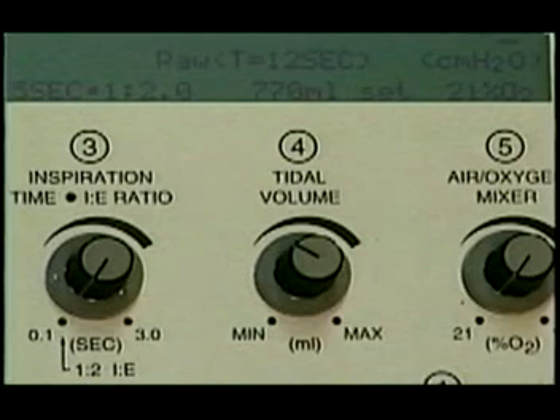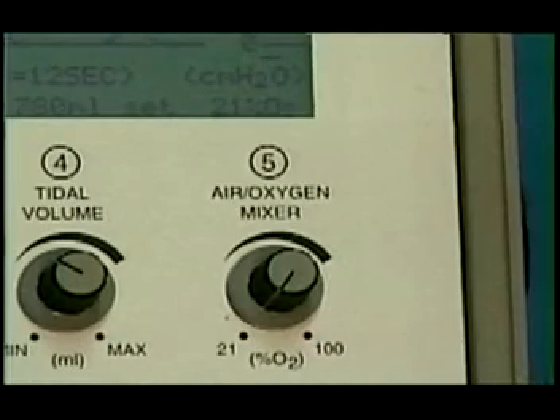The tidal volume control is the control numbered 4 and sets the tidal volume. Its range is based on gas flow not exceeding 60 LPM or 1,000 milliliters a second as determined by the control position. Both set and delivered tidal volume are alternately displayed in the LCD above this control. The air-oxygen mixer control is the control numbered 5. It sets FiO2 when the ventilator is connected to external 50 psi oxygen and operates with the internal compressor or external 50 psi compressed air. Its range is 21 to 100% based on the control position, and the FiO2 value is displayed in the LCD above this control.